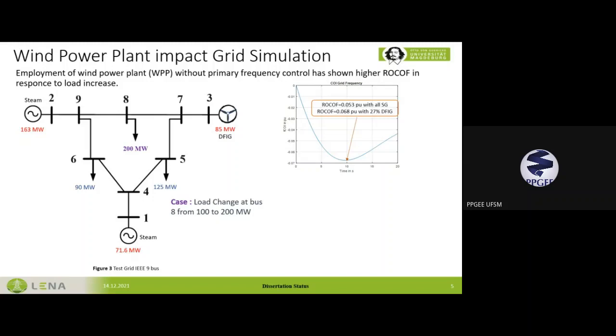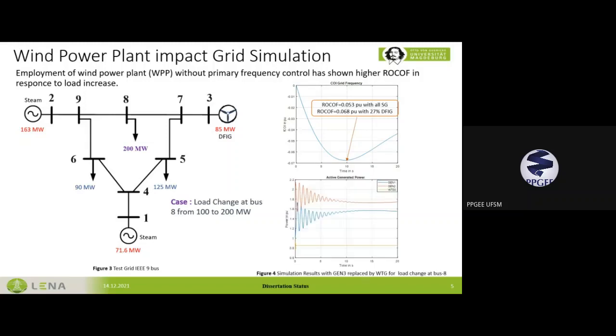This is the problem we have to solve. For synchronous generators, the output increases because of load change—the load increases from 100 to 200 megawatts in this test network. The active power for synchronous generators increases, while for wind it remains constant, because we don't have frequency control techniques for wind power.